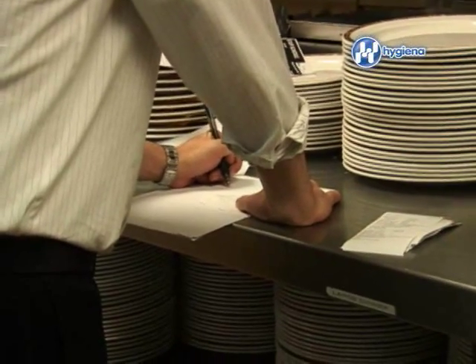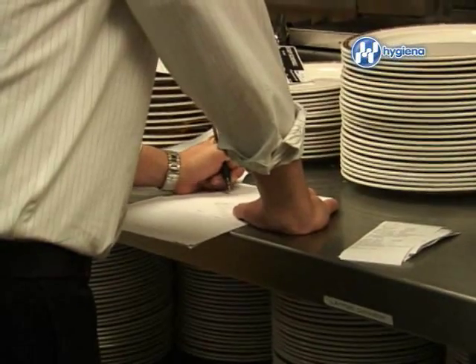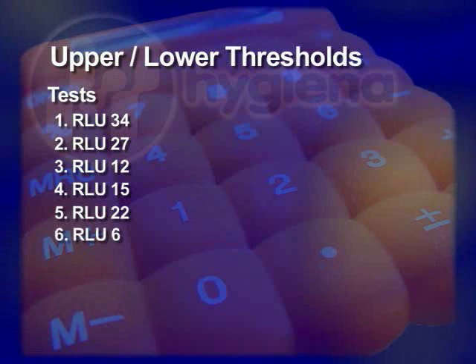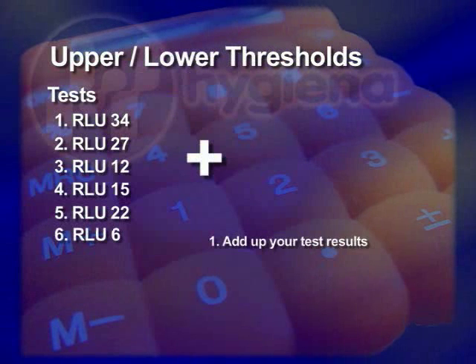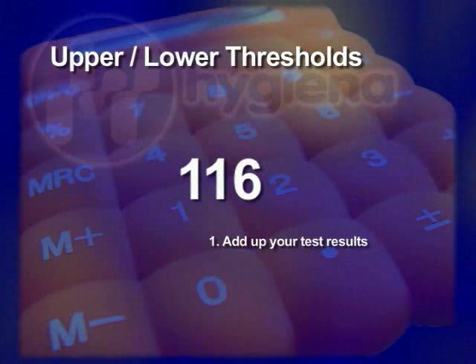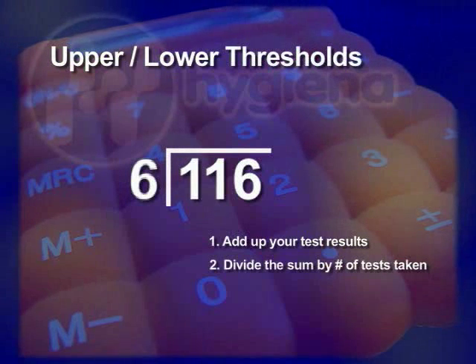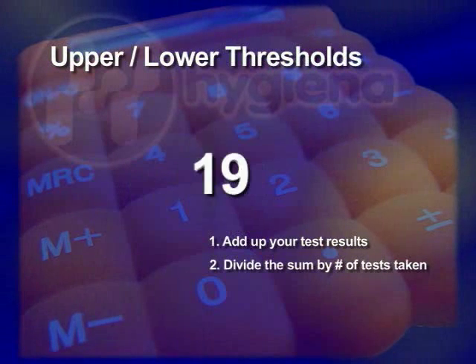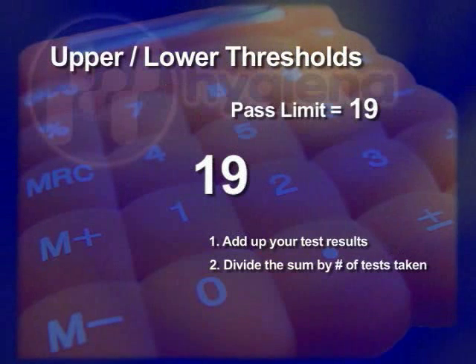After you have performed 5-10 tests, some basic math will be required to find your upper and lower thresholds. To calculate your pass and fail limits, first add up the RLU numbers from the 5-10 tests you took from around your facility. Next, divide your sum by the number of tests taken. The resulting number is your average RLU. This is your pass limit.